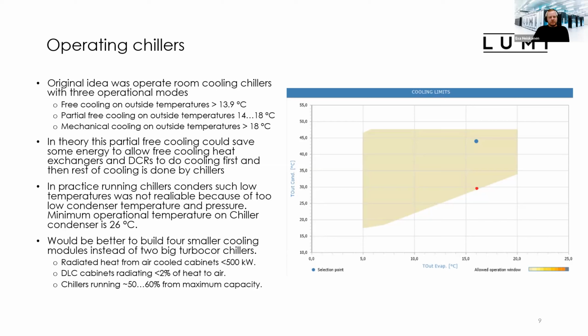So those couldn't be reliably run. So there were some issues with these devices. As you can see from this graph, the minimum operational temperature of this chiller condenser is about 26 degrees, and it couldn't be reached in this partial free cooling mode. So we decided that we are only running our chillers as usual, so only free cooling and mechanical cooling modes.